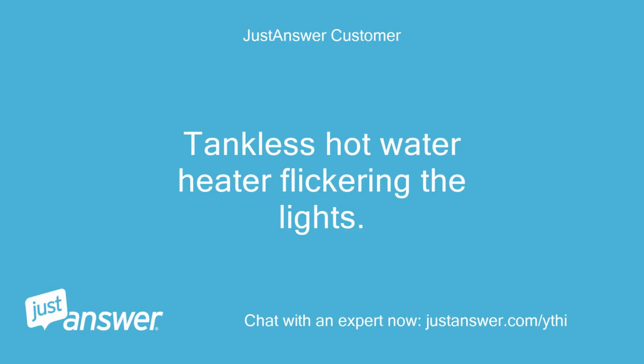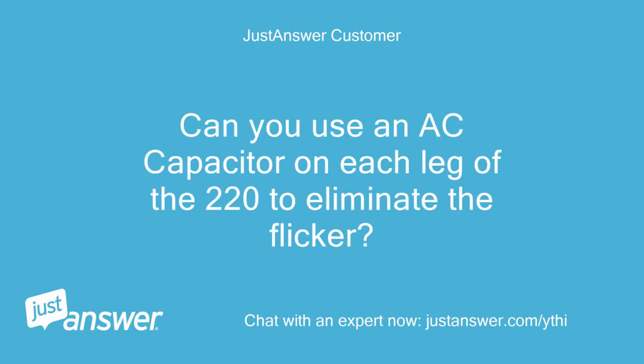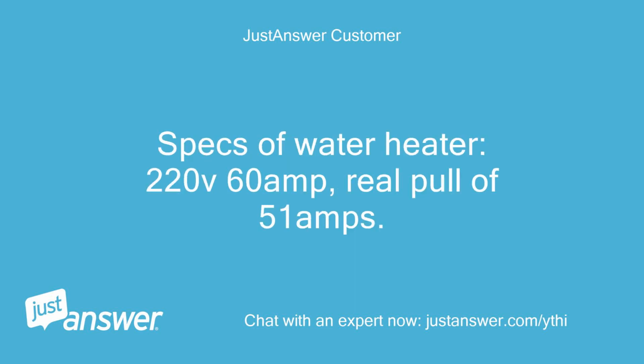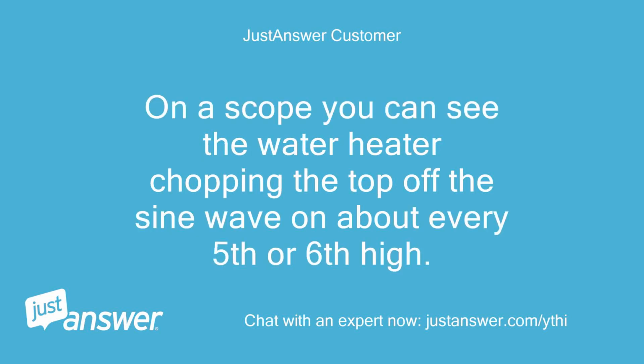Tankless hot water heater flickering the lights. Can you use an AC capacitor on each leg of the 220 to eliminate the flicker? Specs of water heater: 220V 60 amp, real pull of 51 amps. On a scope you can see the water heater chopping the top off the sine wave on about every 5th or 6th high.